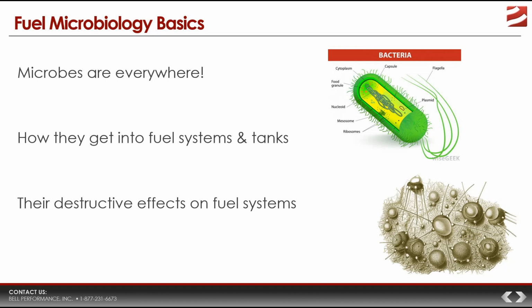And many of these thousands of different kinds of microbes are doing deleterious things to the fuel and the tank systems that they live in. So with respect to their effects on fuel, you have microbes doing things like producing acids that contribute to corrosion problems in the tanks, and also producing these biosurfactant molecules. And the biosurfactants, these are what help create these invert emulsions of water and fuel, which results then in hazy fuel.